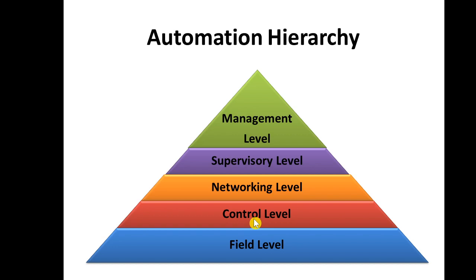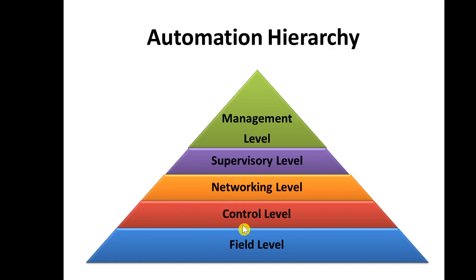The control level may use a Programmable Logic Controller (PLC), a Programmable Automation Controller (PAC), or an embedded controller. The control device is selected according to the field-level requirements — for example, if there are 10 input devices and 10 output devices in the field level, we select a PLC with at least 10 inputs and 10 outputs. If field devices are analog, we need analog inputs or an analog-to-digital converter.